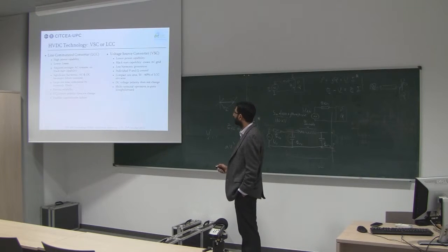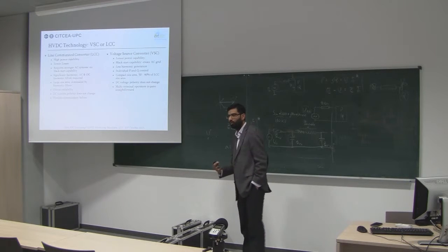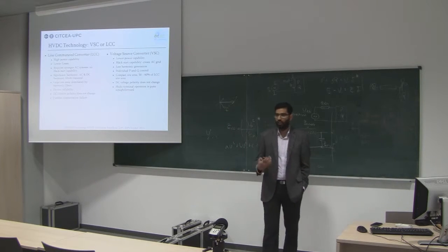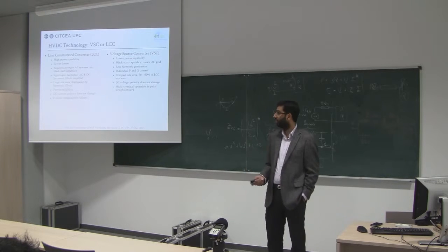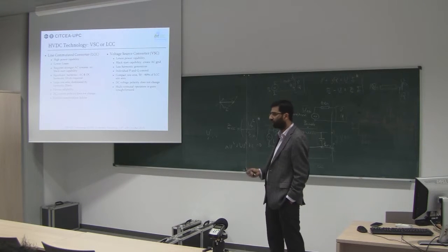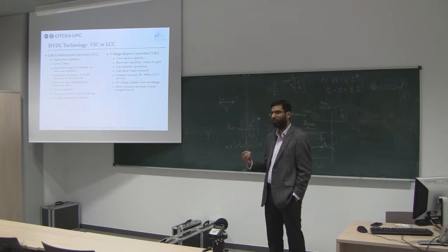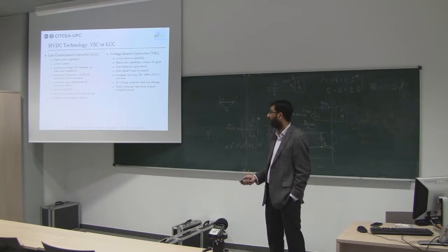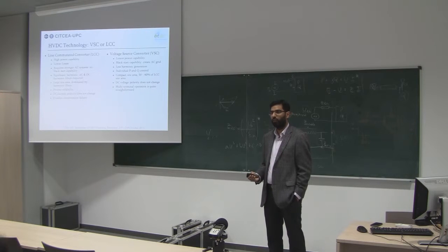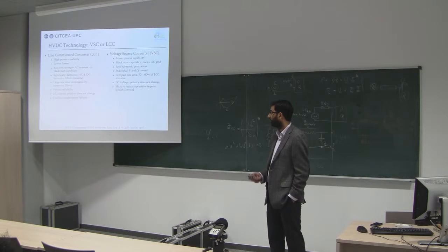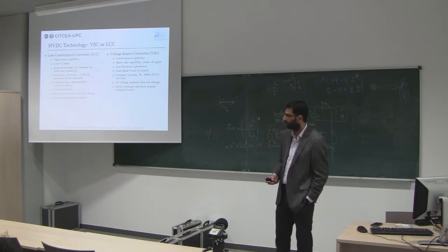A second advantage of the voltage source converter is the ease of changing power flow direction. This is very easy because the voltage polarity is fixed and you're just changing the direction of current flow. Whereas in a line commutated converter, you have to reverse the polarity of the DC voltage level, which is not a straightforward procedure.